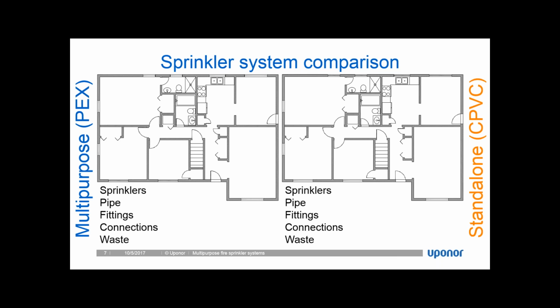All right, so from here on out, if I say PEX, what I mean is Uponor Aquapex piping. From here on out, if I say CPVC, I mean CPVC, because there are a lot of different manufacturers of CPVC pipe. But specifically, the stuff that's rated for fire protection on the CPVC end will be the orange CPVC pipe. It's important to preface that when I say PEX, I mean Uponor Aquapex tubing, because not all PEXs are created equal, and not all PEXs carry a listing for residential fire protection. So you couldn't just go to a Lowe's or a Home Depot or any big box store and purchase PEX tubing and install it in a fire sprinkler application. It has to come with a specific listing, and Uponor's is listed for that specific application.